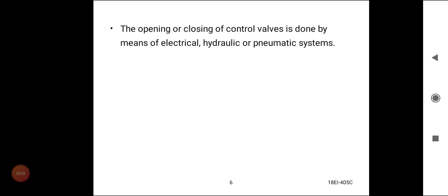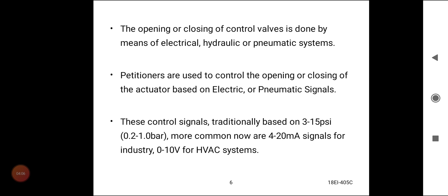Positioners are used to control opening or closing of the actuator based on electric or pneumatic signals. These control signals are traditionally based on 3 to 15 psi, pounds per square inch, that is 0.2 to 1 bar. More common now are 4 to 20 milliamp signals for industry, 0 to 10 volts for HVAC systems.